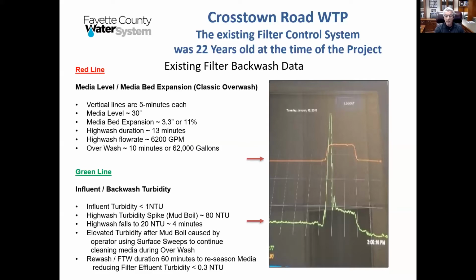What you're looking at in the orange line is the media level in the filter. You can see it rise, that butte, that hump in the red line. That is when the filter has gone into a high wash and it fluidizes the media and it rises. The green line is the turbidity on top of the filter, and during the backwash, the backwash turbidity goes ballistic and right off the screen at the top when they fluidize the bed.